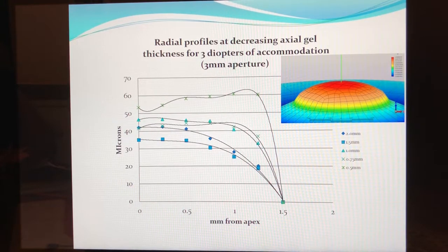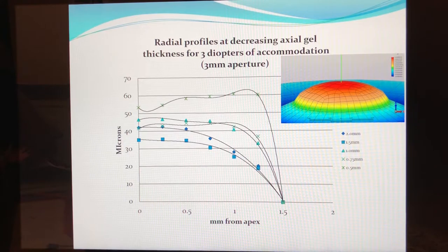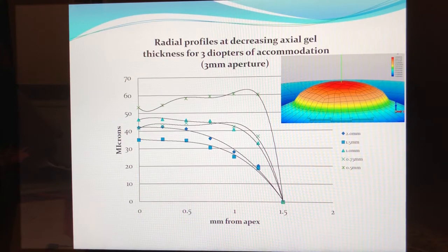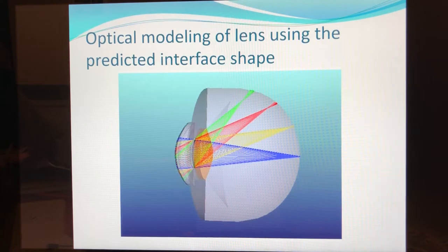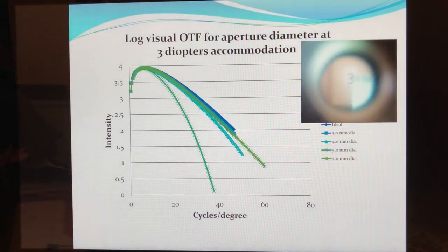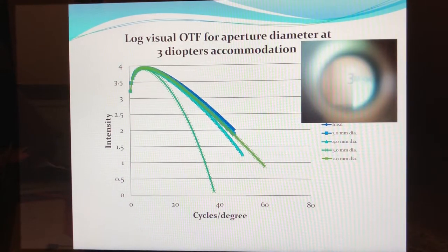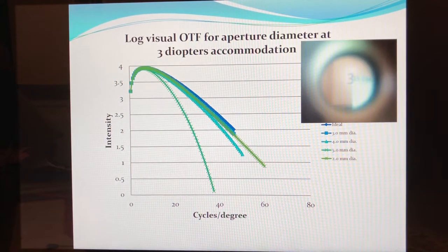What we're showing here is the actual radial surface of the deformable accommodating surface interface as it increases in diameter, and you get some rippling effect as the diameter gets out close to two millimeter radius — four millimeter diameter total. We then use the deformed interface to propagate an aberrated wavefront image to the retina using standard Fourier techniques. The model is then able to produce a contrast sensitivity corrected optical transfer function at the retina and a subsequent visual Strehl ratio, which is our second output metric.